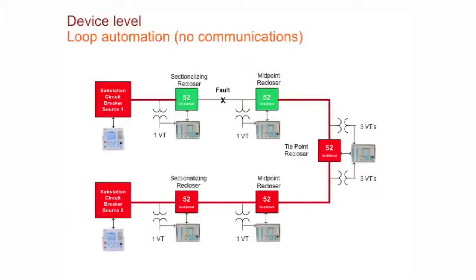So the same case could be implemented using Goose. And I say Goose, it's part of the peer-to-peer specifications of the 61850 standard. So you deploy your communication network. So you have your radios connected to each IED on the network. And basically the same case, if you have a fault here, okay. So this one goes through the reclosing sequence, 1, 2, 3, 4, after the 4th shot, it stays open. The difference now is once it stays open, it sends a message to this device saying, listen, I detected a fault, I went to lockout, I want you to have that information. So this device publishes the lockout message.